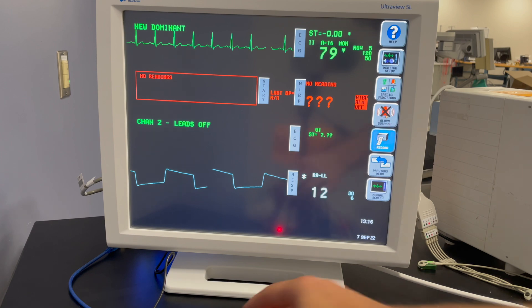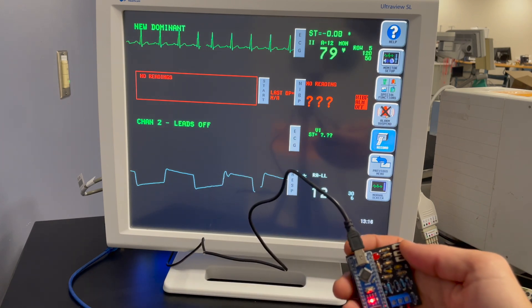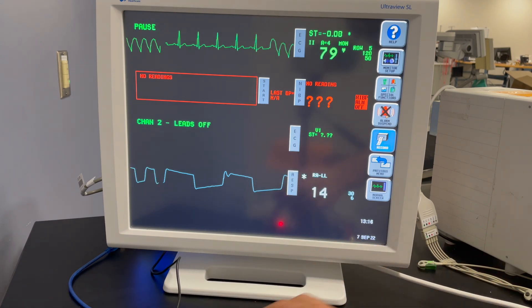If I go ahead and go to my toggle switches on my patient simulator and I flip the bottom two over to the left, once again that's a simulation for tachypnea, you'll notice that the respiratory rate picks up.